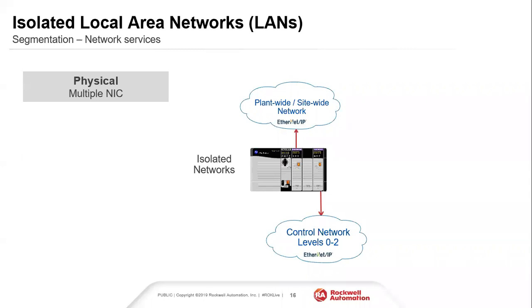So what I typically do, especially in ControlLogix, is segregate and put two Ethernet adapters, one for my control network. This would be all of my IO. I can have Point IO, Flex IO, ControlLogix IO, all dedicated on the bottom. I'll have a secondary Ethernet adapter that's dedicated only to my HMI and my historian traffic. So when I'm connecting via Studio 5000, I connect into this first card so that I can do all my configuration changes. The controller is always using this second card to do its IO traffic. So anything that I do on that first card is never affecting the traffic that I'm doing for the IO. If I'm sending a command to a pump to turn on, I don't have to worry about what I'm doing on the top end side.